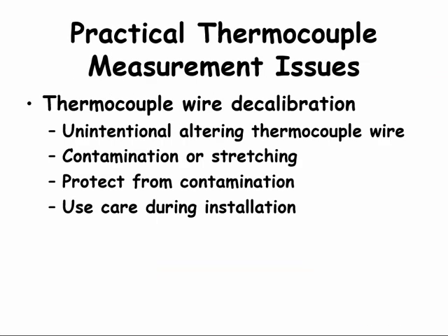Another thermocouple measurement issue can be caused by thermocouple wire decalibration. Wire decalibration occurs when thermocouple wire is unintentionally altered in some way. Wires can be altered by stretching, which makes the wire thinner. Wires can also be contaminated if the wires go through a corrosive or contaminated environment. Thermocouple wire decalibration can be mitigated by protecting wires that go through a corrosive or contaminated space. The other key thing to do is use care when installing thermocouple wires. This concept applies to other signal wires. Be careful when installing them and protect them when they go into a corrosive or contaminated space.